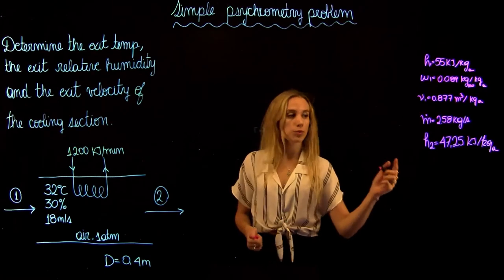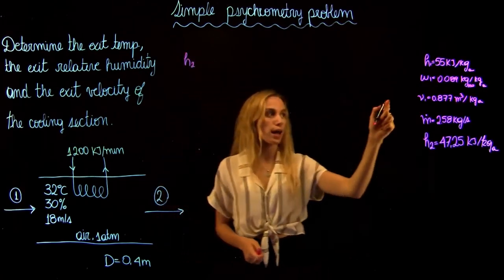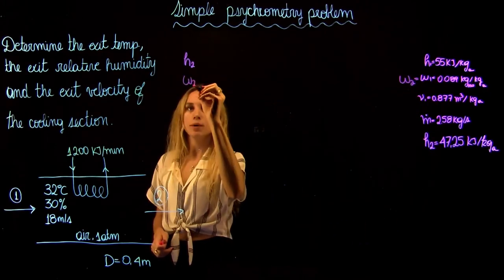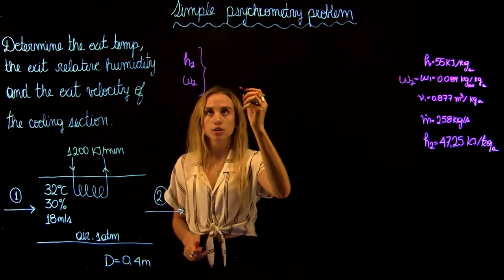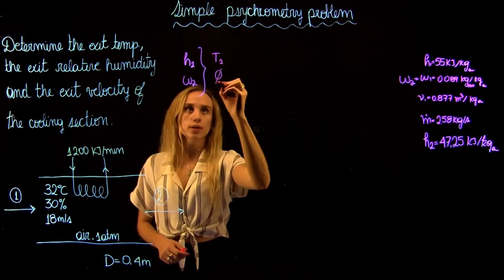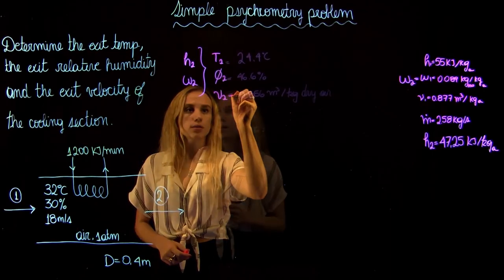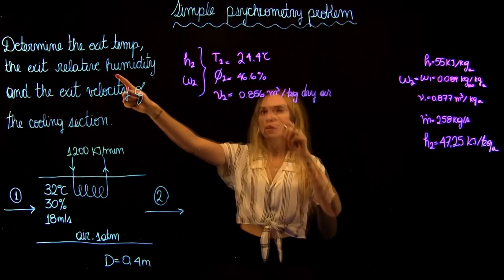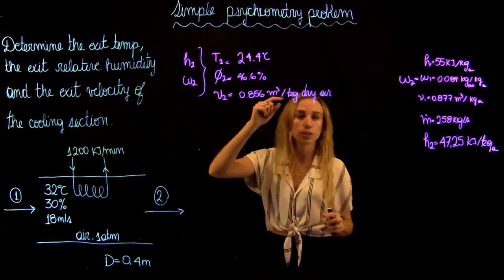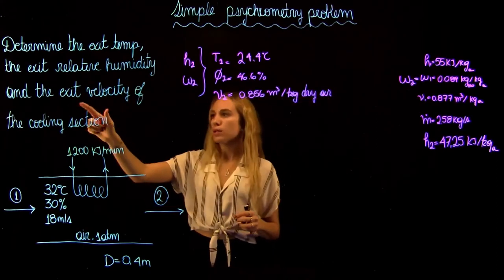Now we have two known values at state 2: the enthalpy and the absolute humidity, which remains constant. Using these two values on the psychrometric chart, we can find the exit temperature (dry bulb temperature at state 2), the relative humidity at state 2 which is 46.6%, and the specific volume at state 2.